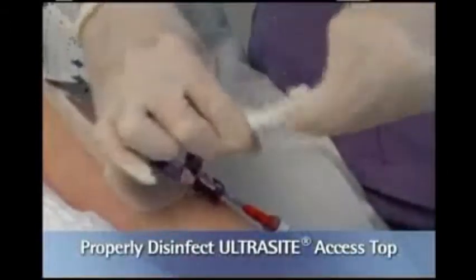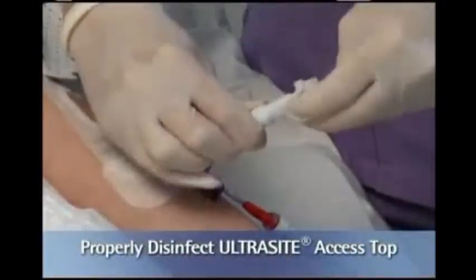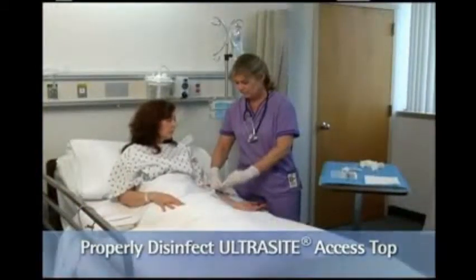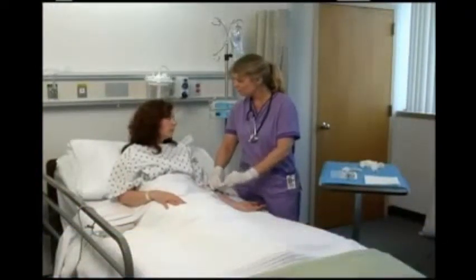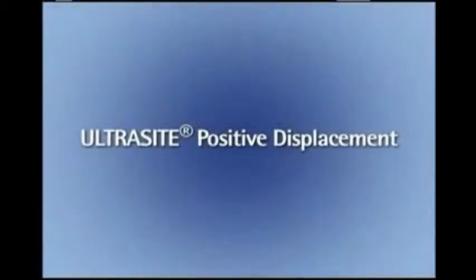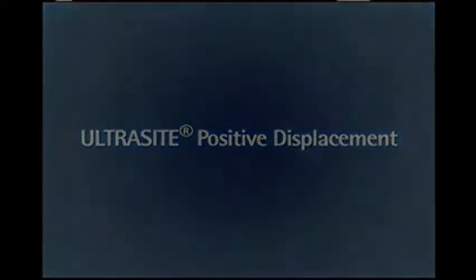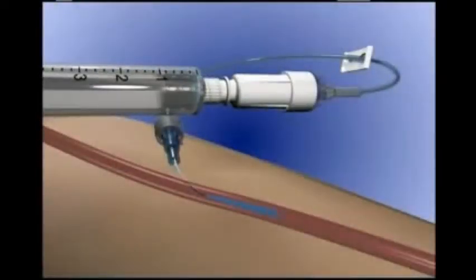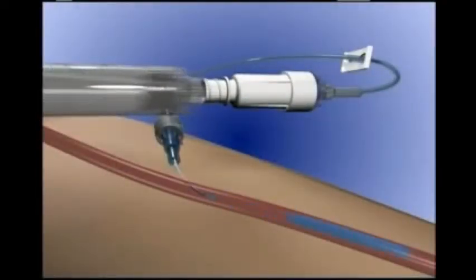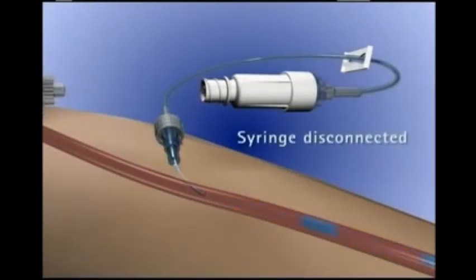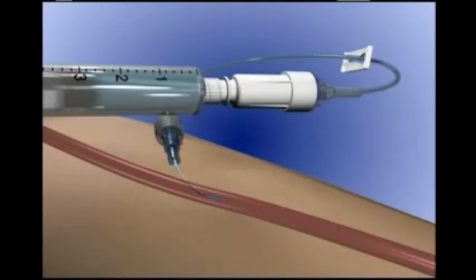During this procedure, the clinician continually follows best practice by disinfecting the Ultrasite Luer Guide access top with alcohol before attaching each flush solution syringe and after disconnecting the final syringe. The innovative Ultrasite positive displacement feature must be seen in detail to fully appreciate how it decreases the risk of catheter occlusions. The positive displacement feature automatically pushes a small volume of fluid through the catheter when a Luer syringe is disconnected from the Ultrasite Luer access device. Let's watch that again in slow motion.